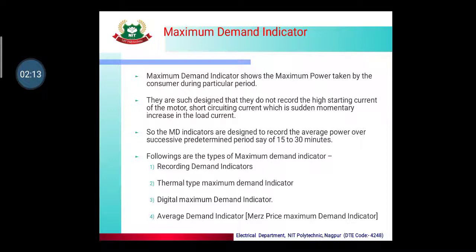Maximum demand indicators are designed such that they do not record the high starting current of a motor or short circuiting current, which causes a momentary increase in load current. Instead, maximum demand indicators are designed to record average power over successive predetermined periods — say 15 to 30 minutes.